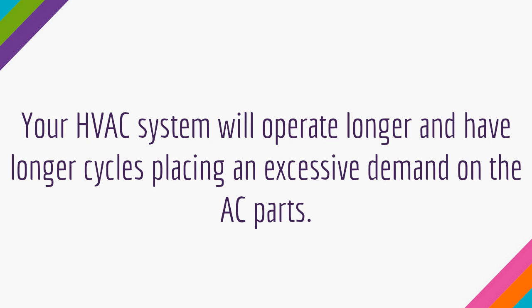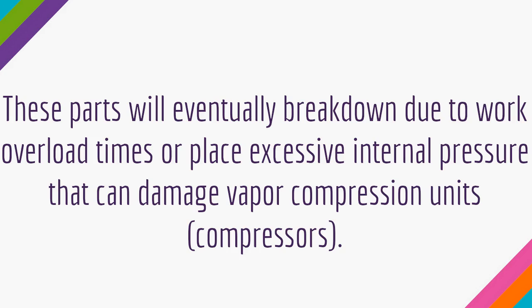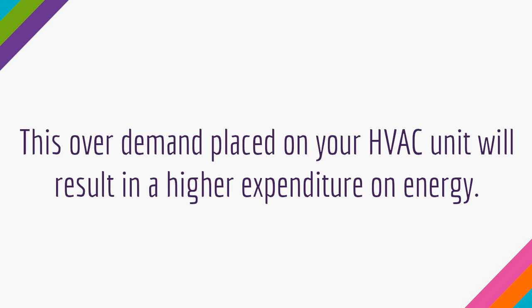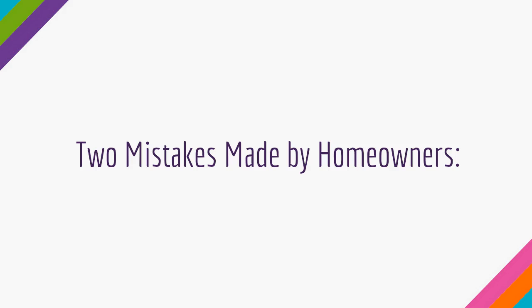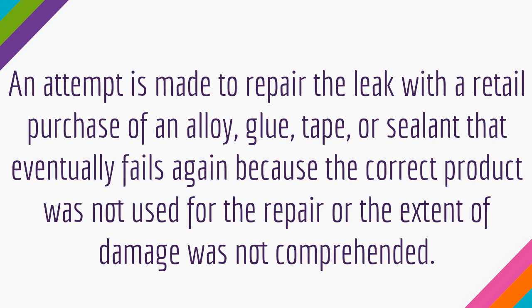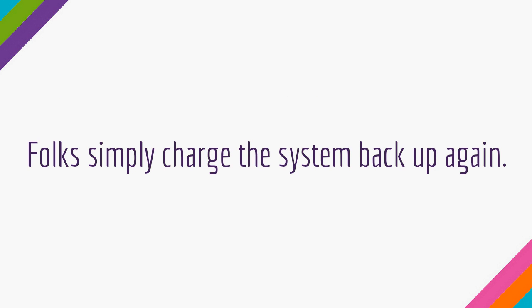Your HVAC system will operate longer and have longer cycles, placing an excessive demand on the AC parts. These parts will eventually break down due to work overload or place excessive internal pressure that can damage vapor compression units or compressors. This overdemand placed on your HVAC unit will result in a higher expenditure on energy. Two mistakes made by homeowners. An attempt is made to repair the leak with a retail purchase of an alloy, glue, tape, or sealant that eventually fails again because the correct product was not used for the repair or the extent of damage was not comprehended. Folks simply charge the system back up again.